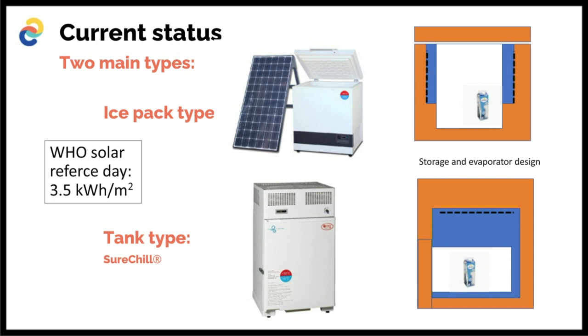The storage is in the form of a large water tank surrounding the compartment, and the evaporator is in the top of this water tank. So when we start cooling, we build up ice in the top. Water has this strange phenomenon where water at 4 degrees C has the highest density, so when the water is cooled, it falls down around the storage volume or the compartment. This means we always have around 4 degrees C around the compartment, which is a very elegant way to have passive temperature control.